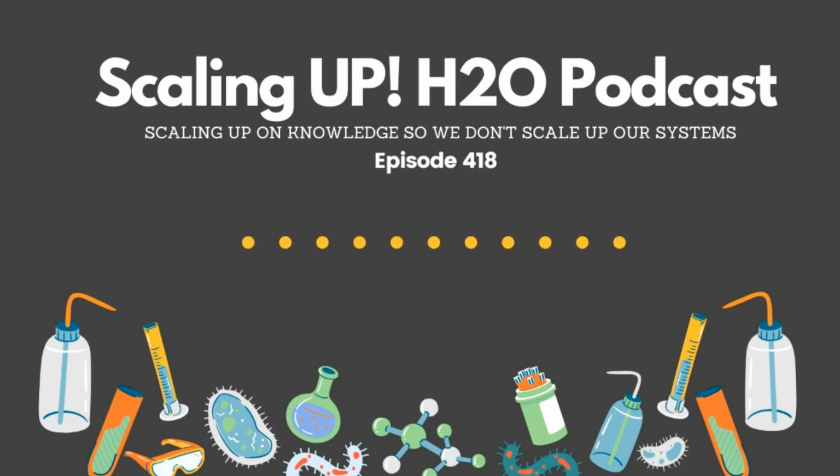It can go either way. You've got to really be careful, because one of the things that people a lot of times don't think about when they're doing lab testing of corrosion inhibitors is making sure that the surface area of the coupons being used versus the water volume is consistent with what you might see out in the field. If you get that kind of right, then your dosage demands can be pretty close. If you get that a little bit out of whack, then you could either underestimate or overestimate how much corrosion inhibitor is necessary. I'll ask water treaters that'll try a new product, and 9 times out of 10, I'll get some sort of sensational reply.